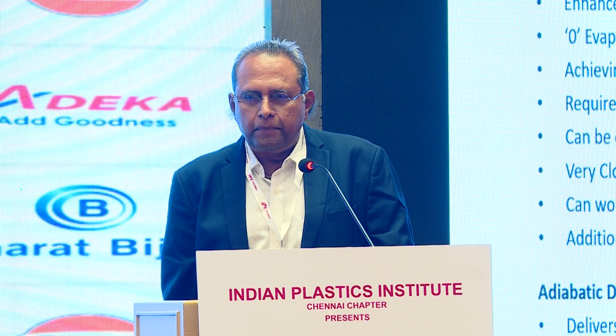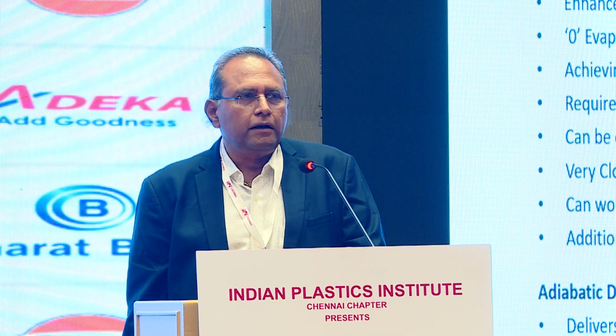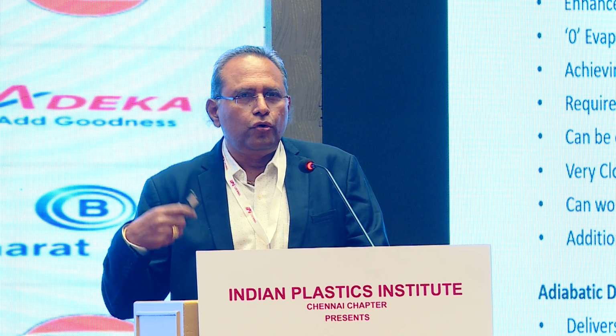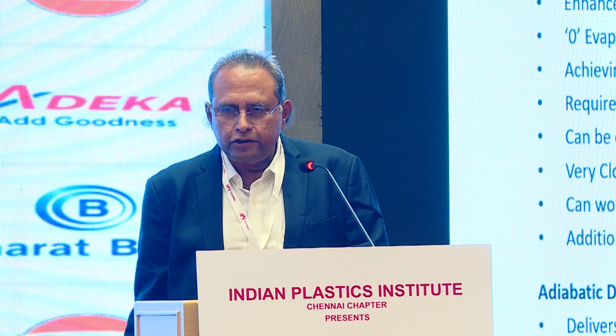Similarly, the process water temperature with varying loads can be held to plus or minus 0.5 degrees centigrade. Because you are giving a very consistent temperature to your process, whatever you produce will also have an accurate quality of finish. And all these equipments are designed to work for 50 degree ambient, so you don't have to go for a water cooler which people conventionally use. And by properly selecting piping sizes, a lot of energy can also be conserved on the pumping pressures.